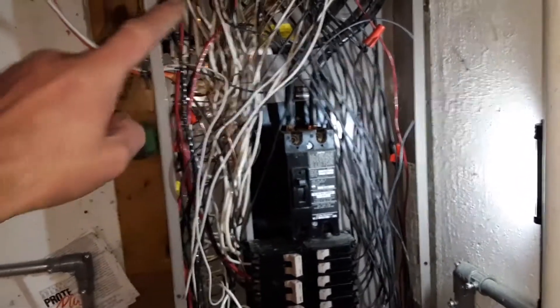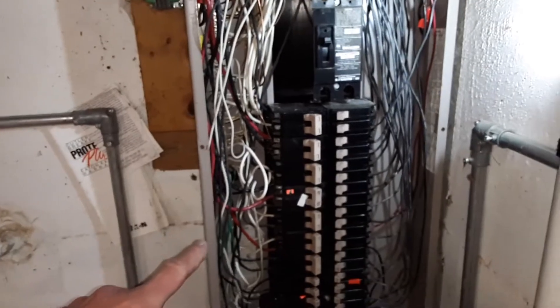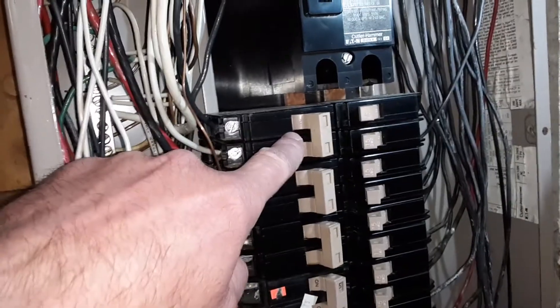A couple of items I found: not only are the wires not clean and straight coming into the panel to the breakers and into the lugs as they're supposed to be, but I also noticed over here there's a double-pole breaker and then another double-pole breaker.